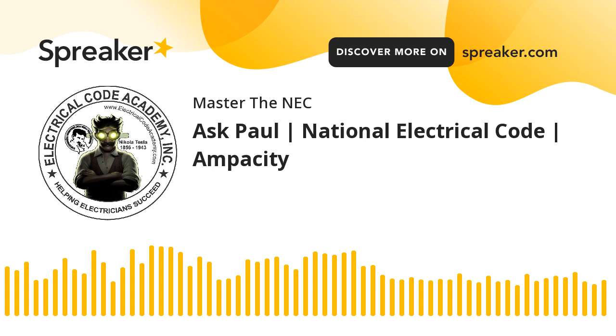All right. So the other thing that I want to talk about, shifting a little bit, is the term continuous load. Another thing that students sometimes have to wrap their head around is that when we say something is a continuous load, so if I tell you we have 40 amps of continuous load, the actual load in question is 40 amps. But I'm telling you it's continuous. So it's going to be pulling those 40 amps continuously for 3 hours or more. So that's the first thing to think about.